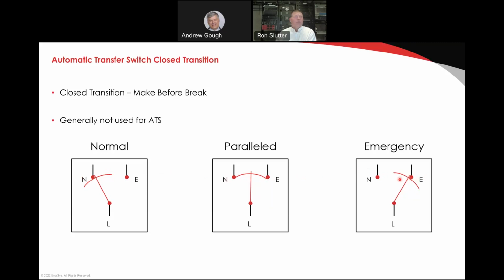Why do we use this? We use this to make sure that we don't drop downstream loads. However, when we do this, it can create unique issues related to the phasing. All of the sources have to be phase matched. Otherwise, we would or could put phase A to phase B, which is a dead short. So we have to be very careful.